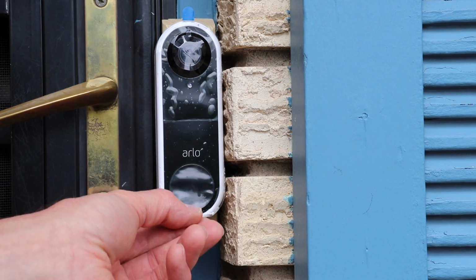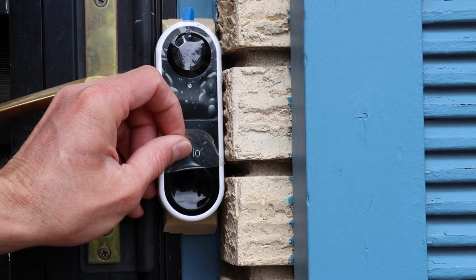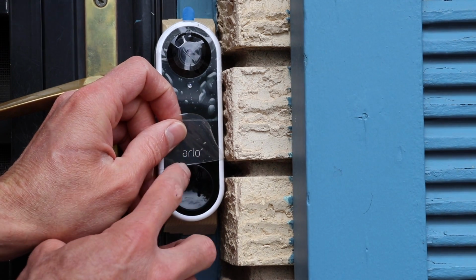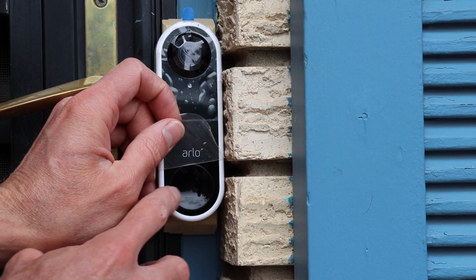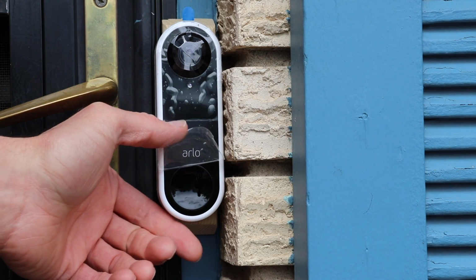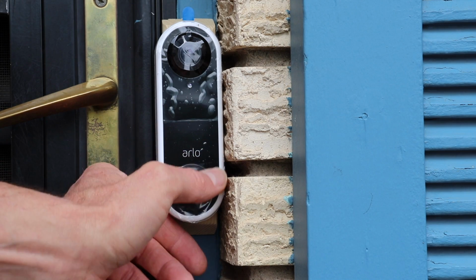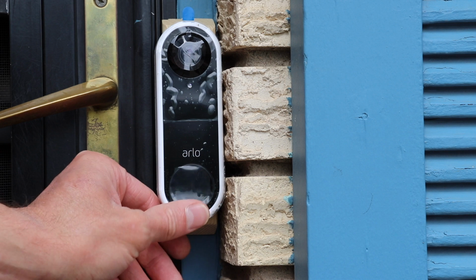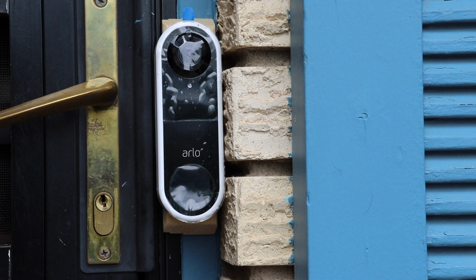Okay, so I got it all hooked up, and I'm getting these amber colored lights around the dial here, around the button. I looked at the troubleshooting, and that means it's improper voltage. I tested the lines and I'm only getting 10 volts. So we need to locate and replace the transformer with a 16 to 24 volt transformer.